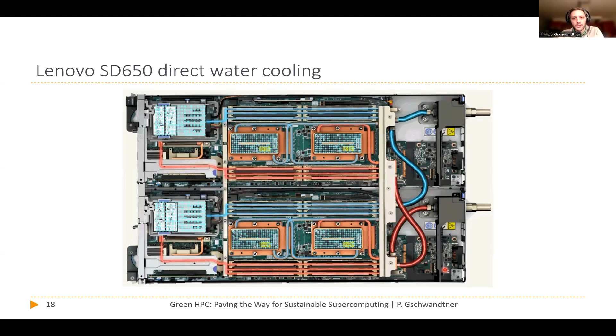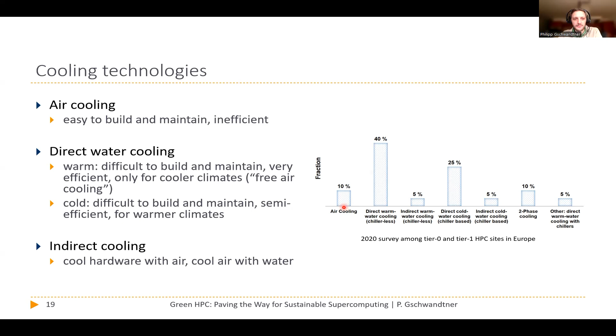On the right, you see a statistical overview of a 2020 survey among the largest supercomputing sites in Europe. The majority use direct warm water cooling because it's the most energy efficient solution we know, besides oil cooling, which we don't do anymore. Next is direct cold water cooling, probably the next most efficient, except you have to actively cool the water down. All the others, like air cooling and indirect cooling, are only in the 10 or 5 percent share range, simply because they're not that efficient.